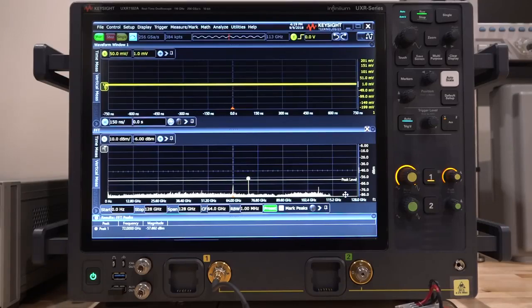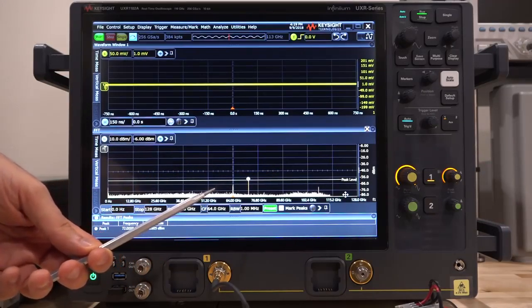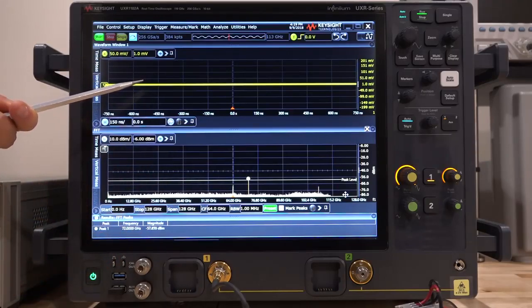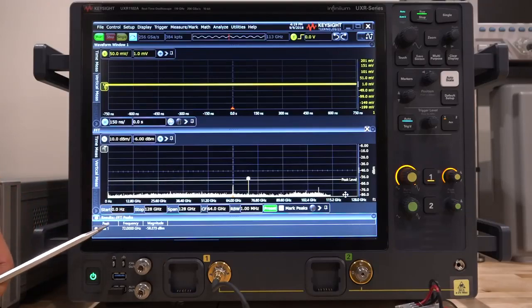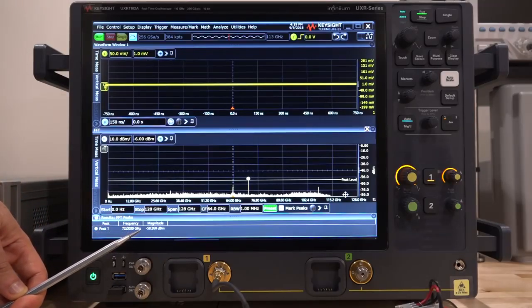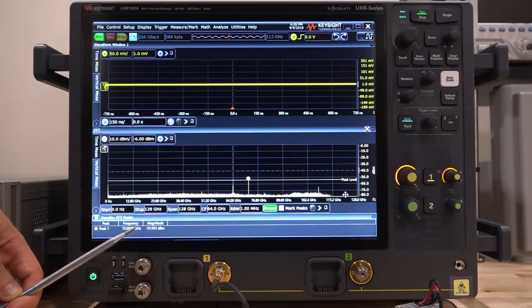There it is. Now you can see as soon as I turn the signal on, there are some additional tones appearing in the FFT. You don't see it at all in the vertical here because it's so small, but we can see that the instrument is capturing a signal at 72 gigahertz at minus 58 dBm. But 72 gigahertz is 18 times 4. It's not 18 times 6, which means that this multiplier right now has a larger times 4 output than it does a times 6.